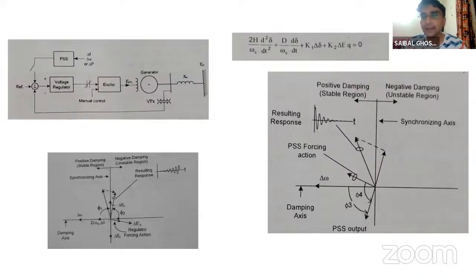And how PSS acts: based on whatever deviation there is from the speed, or you can say the delta, PSS introduces some excitation voltage in the opposite direction. So again the overall resultant of all the operating forces turns into the positive damping quadrant and positive synchronizing quadrant, and that's why the resultant response again stabilizes.